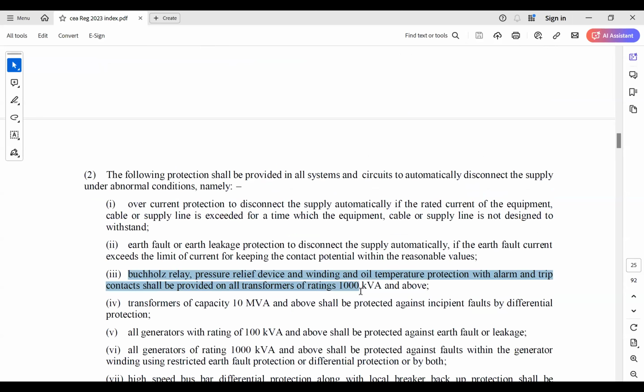Yes, correct. Point number three states that the Buchholz relay, pressure relief, and oil and winding temperature protections are to be provided beyond 1000 kVA transformers. On the other hand, it is a widely known fact that all these protections or safety systems can be provided with the help of a circuit breaker only. So the question that comes to our mind is: why mandate a circuit breaker below 1000 kVA? Because if we don't provide all such protections in the installation, that circuit breaker is also going to serve the similar function of the earlier switch fuse unit.